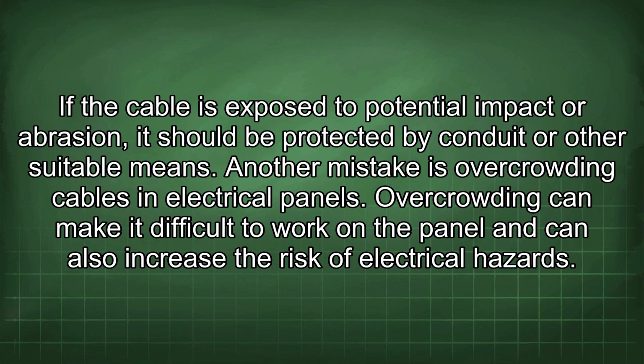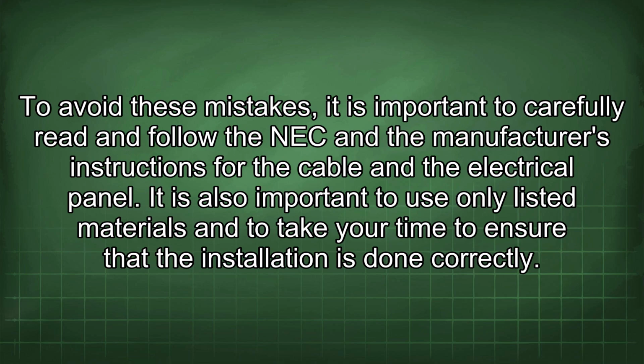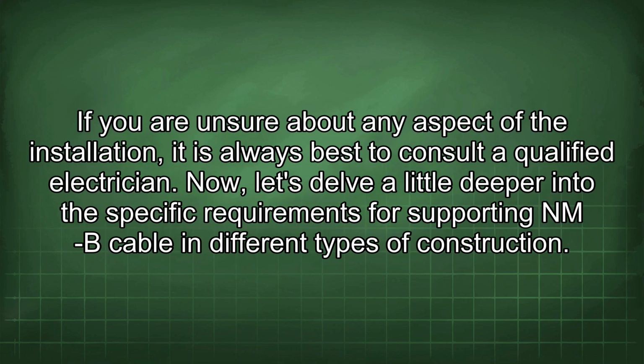Overcrowding can make it difficult to work on the panel and can also increase the risk of electrical hazards. To avoid these mistakes, it is important to carefully read and follow the NEC and the manufacturer's instructions for the cable and the electrical panel. It is also important to use only listed materials and to take your time to ensure that the installation is done correctly.